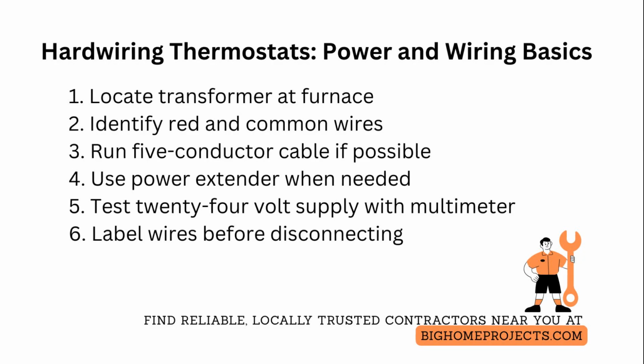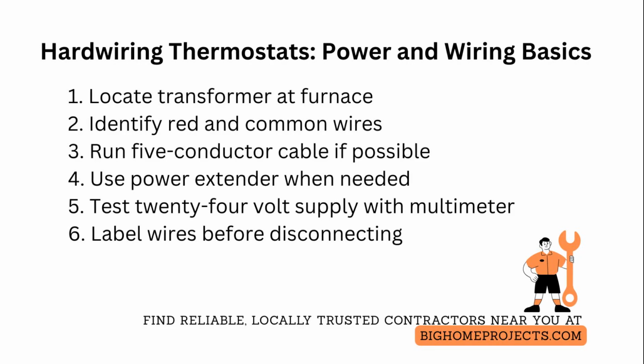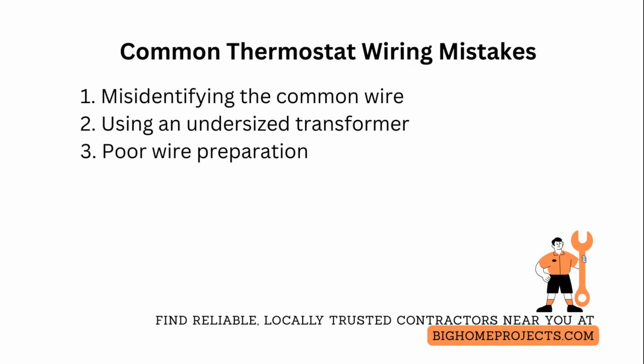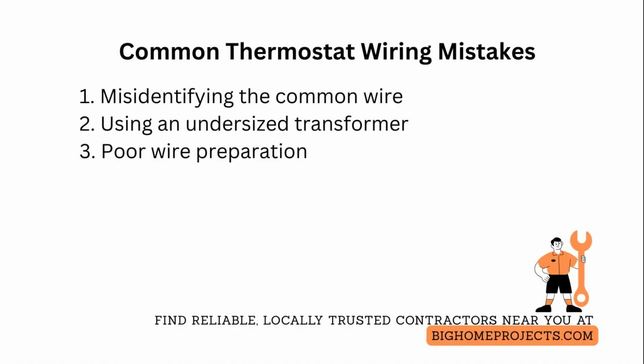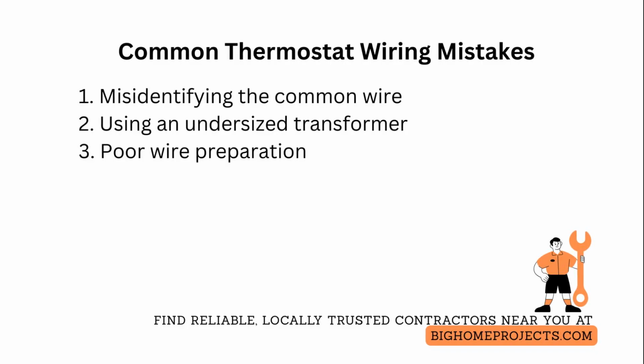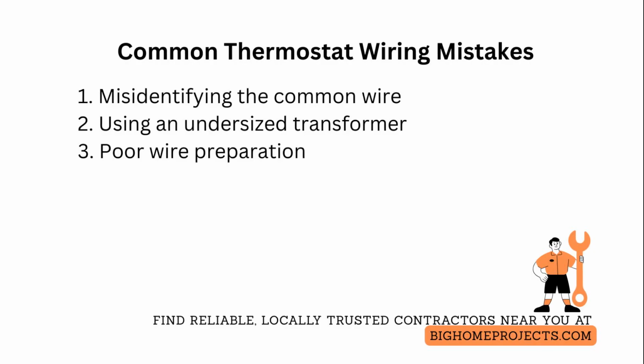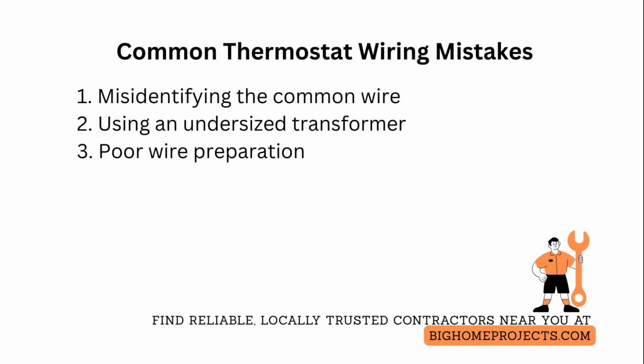Always shut off power at the service switch and tag it, then double-check with a non-contact voltage tester before touching terminals to eliminate risk of shock or shorting sensitive control electronics. One of the most common thermostat wiring mistakes is misidentifying the common wire when troubleshooting and leaving the thermostat dependent on batteries, which results in smart thermostat reboots and loss of scheduling. Fix it by tracing the cable to the control board and confirming the wire on the C terminal is a true common and not a switched or sensor line.